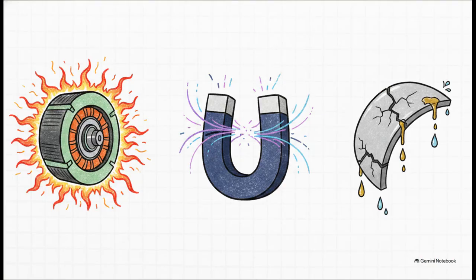So what actually happens when you demand that extreme torque? Boom, massive phase currents generate severe local heating, something engineers call Joule heating. And this attacks the motor on 3 fronts, like a triple threat. First, it pushes the stator core and windings way past 130 degrees Celsius. Second, it fundamentally alters the motor's electrical properties. And third, when you combine all that heat with high-frequency vibrations, this thermal fatigue actively degrades the insulation and seals. That invites oil and moisture right in, creating high-impedance short circuits.